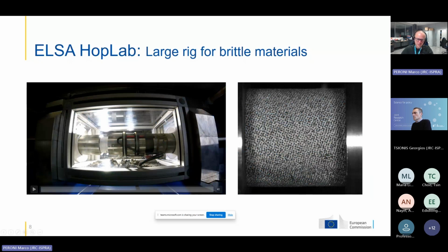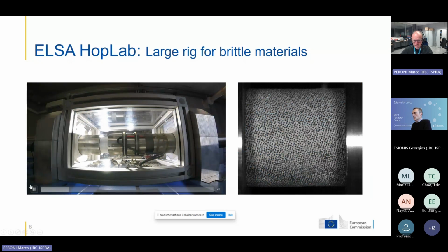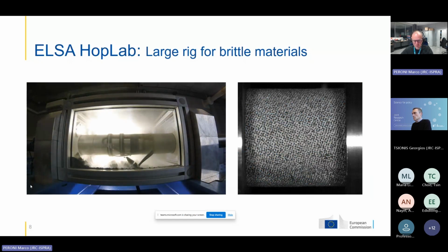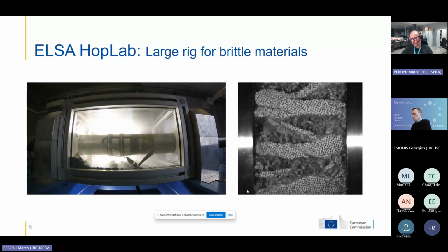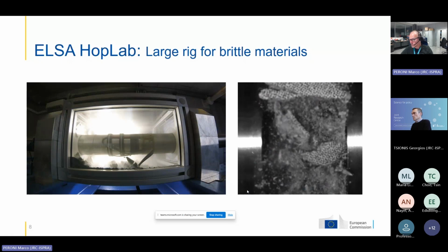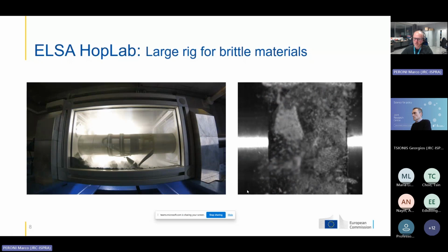You can see here the specimen on the left, a cylinder of 10 centimeters of diameter and 5 centimeters of length. This is a video at real velocity. You see that the test lasts very few instants, and with your eyes it's practically not possible to see anything. But on the right, you have a high-speed recording, and you can see that it is feasible also to apply digital image correlation or to track the movement of the machine during this kind of phenomena that lasts less than 1 millisecond, sorry.